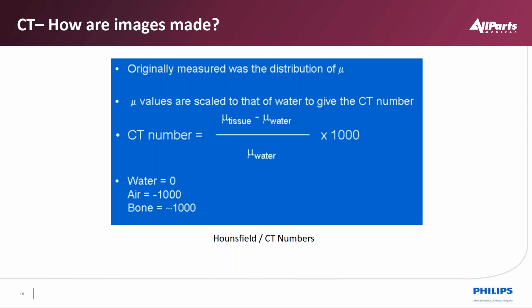In most cases, that's 4 CT numbers plus or minus. Air is a -1000, and air changes daily, so we have to calibrate our machines. So air cals are updated almost on a daily basis as we get the scanner ready to scan patients. We do tube warm-ups and air cals on a daily basis.